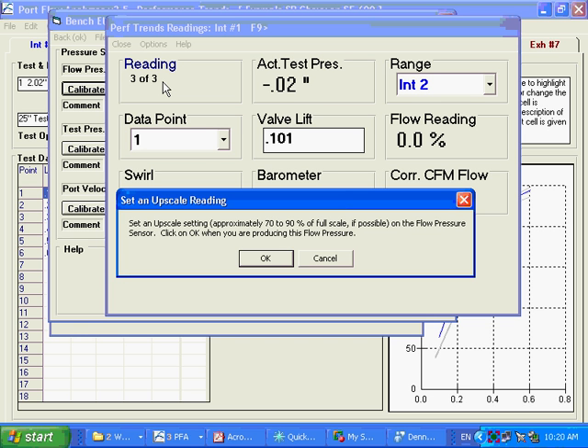So what we're going to do is we're going to produce that condition, and then we're going to click on OK. And this is the critical thing. You must click on OK while that 85% or whatever you set is being produced. Don't set the thing and then shut the bench off and then click on OK. You've got to click on OK while that pressure is being produced, because clicking OK is the program signal that I'm producing that pressure. So produce the pressure, then click on OK.